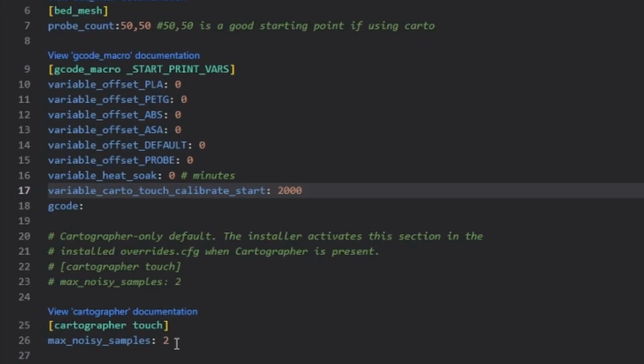Max noisy samples, the default setting is 2. What that means is it will try and do multiple sets of 10 touches. As it goes through those 10 touches, it looks for 3 readings within a certain tolerance. It needs to find those 3 readings within a subset of 5 touches, because it allows 2 of those samples to be out of range. If you set this to 0, it will have to find 3 consecutive touches within that range during that 10 sample subset. So I'm going to change this to 0.